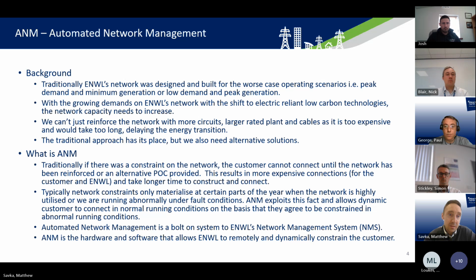Typically, the constraint often only occurs at certain times of the year, when the networks are highly loaded, or running abnormally under a fault condition. What ANM does is exploit this fact and allows customers who are willing to be dynamic with their load to connect under normal running conditions, on the basis that they will agree to be constrained during abnormal running.